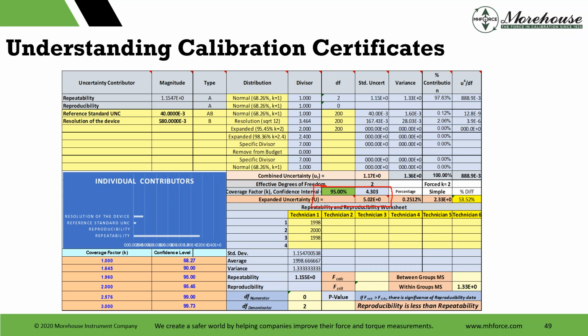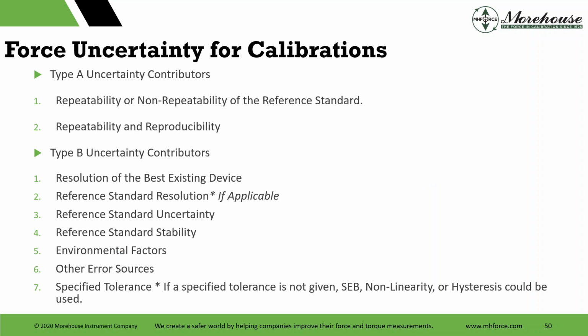Now in this case, since we're just using the resolution and the reference standard, we're not really going to have repeatability, and since we're using combined uncertainties, our degrees of freedom are likely going to be high, and therefore multiplying by 2 would be okay. I just wanted to show this slide because it's very, very important when you're doing your uncertainties, when you're doing your repeatabilities, and you're taking multiple measurements, that you're really considering the impact of the degrees of freedom in relation to the measurement to get the appropriate coverage factor for 95%. And just root sum squaring and multiplying everything by 2 on your level when you're doing uncertainty analysis is not going to be good enough.